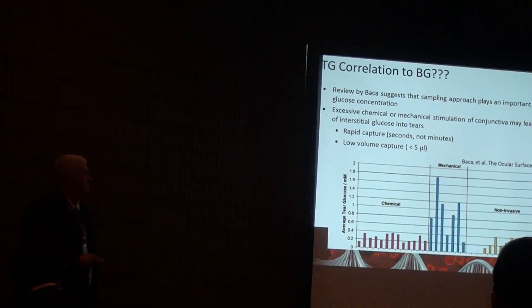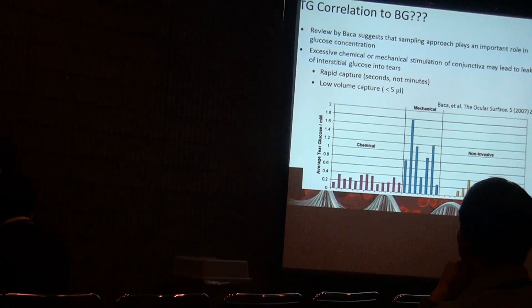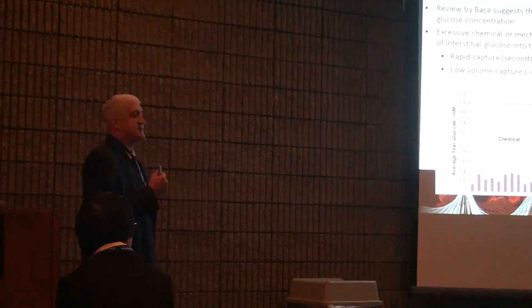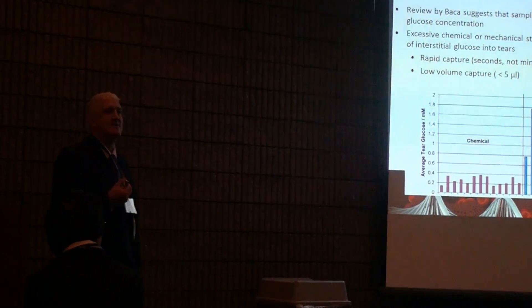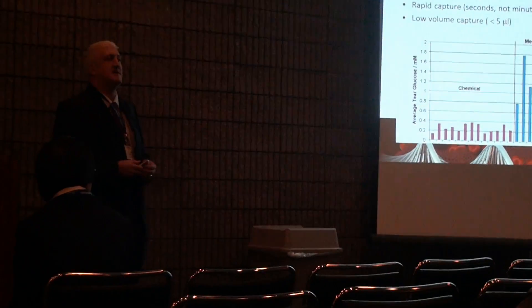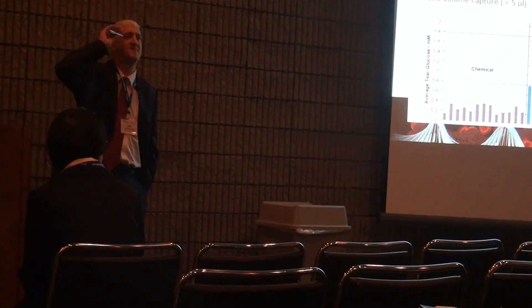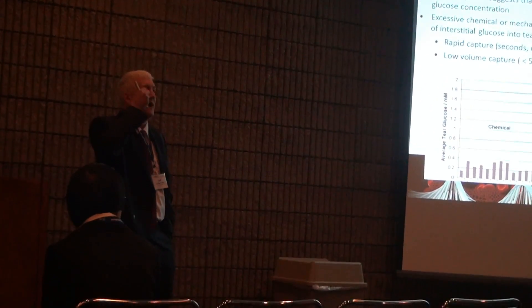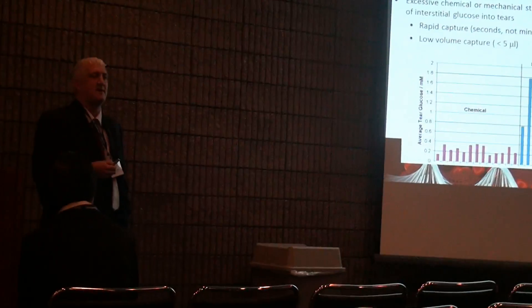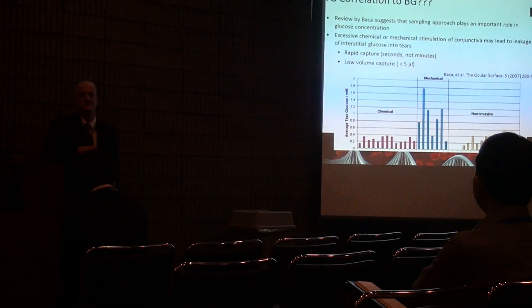Baca put together a wonderful report — the data goes back to 1937 — and researchers tried different methods of acquiring tear fluid from patients. Some of the challenges were actually in acquiring the tear fluid itself. A stress-induced response in the eye is actually mediated with a higher glucose reading. One group used an onion on a person's face to get more tear fluid, which caused a faulty reading with glucose off the scale. Rubbing the eye is a bad event. Some people put a glass capillary on the eye and held it there for five minutes to acquire enough tear fluid — kind of scary. Others came up with novel techniques to get a small volume off the eye, but had evaporation problems leading to faulty readings.